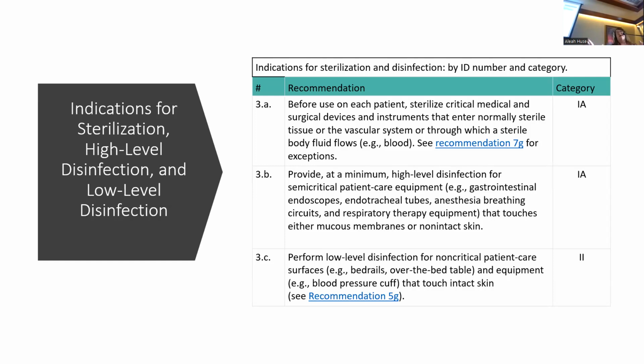I mean, the patients that could potentially have been affected by that is why it becomes an immediate jeopardy type situation. And so having that conversation, knowing that we understand exactly what that chemical is intended for, if it needs heat to be activated, that would require sterilization through an autoclave system. So really being sure that when we pre-soak, when we sterilize, we know exactly what we're using and what's required to hit sterilization, not just high-level disinfection. Okay.